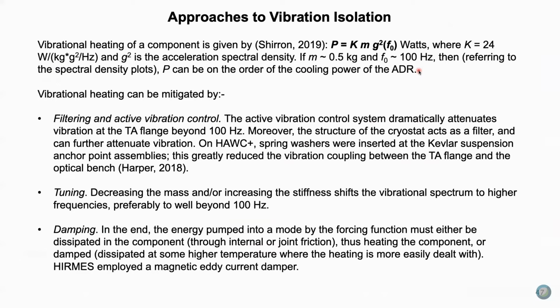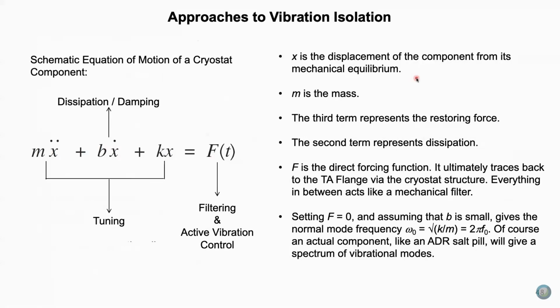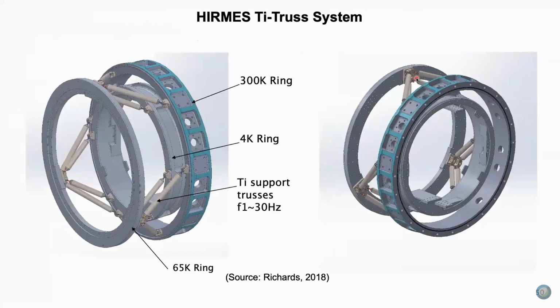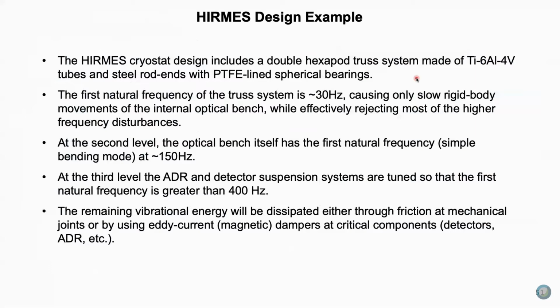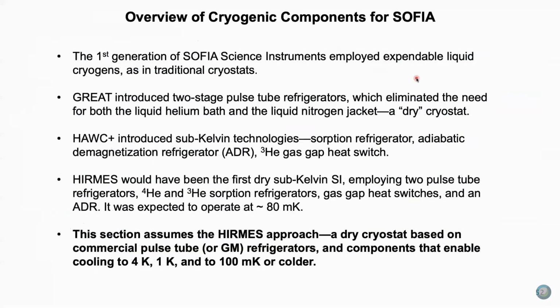This is really only a problem at very low temperatures. At low temperatures, if you get into a situation with vibrational heating, it can very easily eat up all of your available cooling power. You're only starting with 1 or 2 microwatts of cooling, and you can easily get that much vibrational heating. So if you're working at very low temperatures, you have to be very careful about vibration.